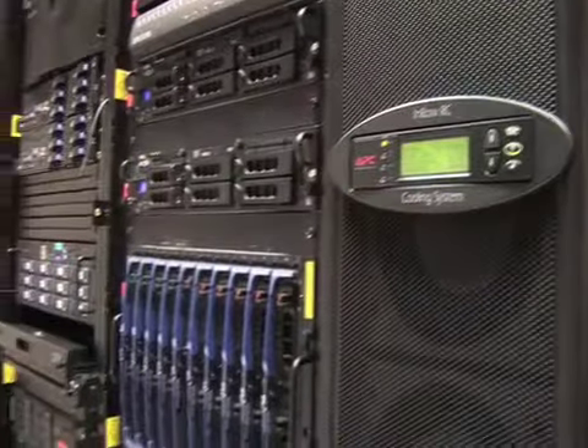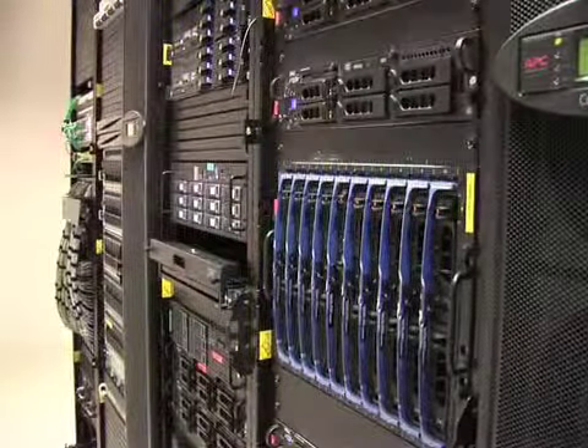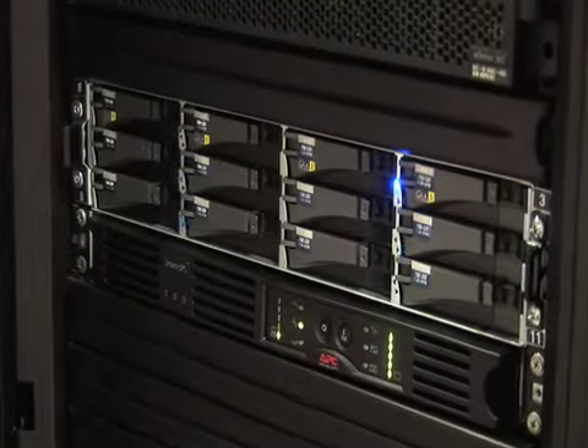The first technology was the APC UPS. Instead of what we were doing, with single units in racks as our UPS system, they suggested centralising all the UPSs into one central unit. If we implemented that, we would get N+1 redundancy, meaning any failure of one unit would not bring down any of our current racks, which seemed good. Not only that, it was also very space efficient, so that seemed like a great solution. And the power requirements were actually less than what we were intending to implement. So that was issue number 1 ticked off.